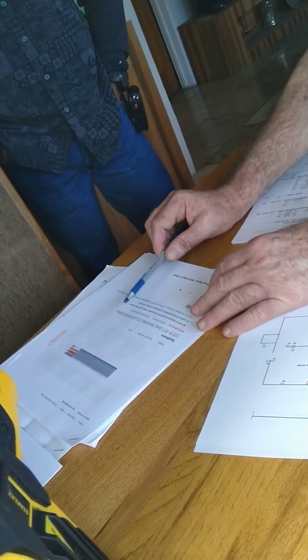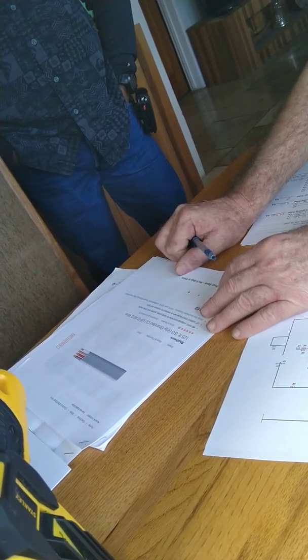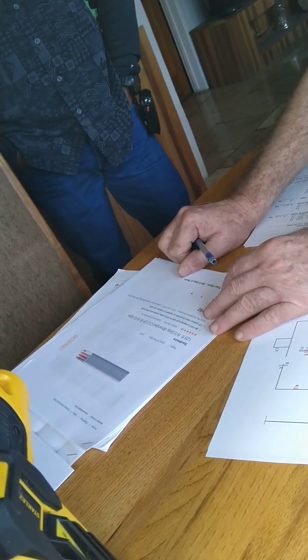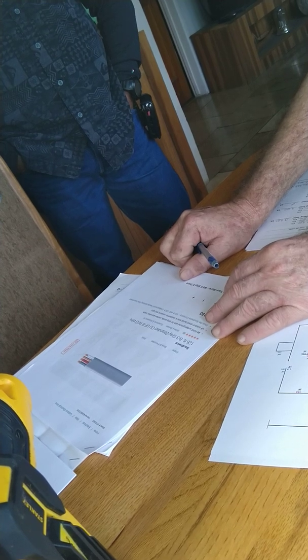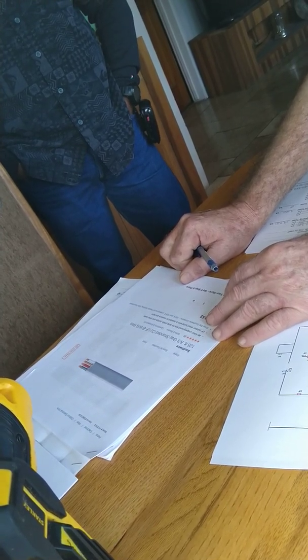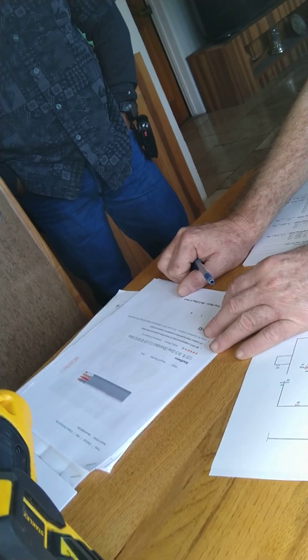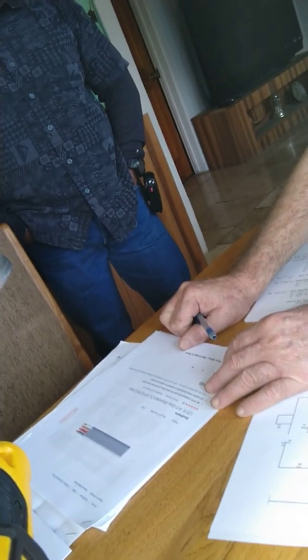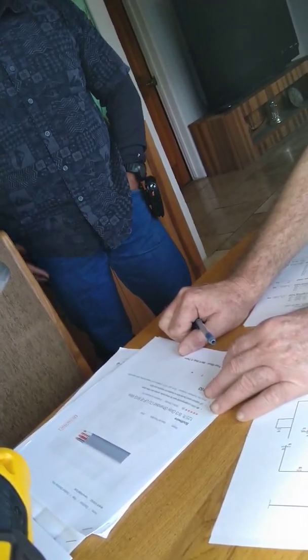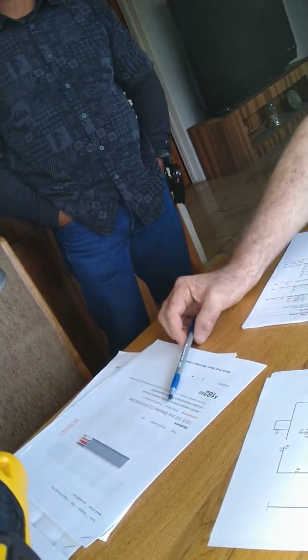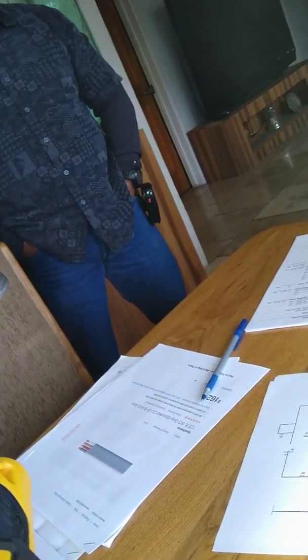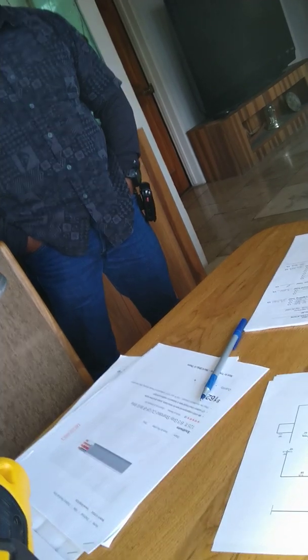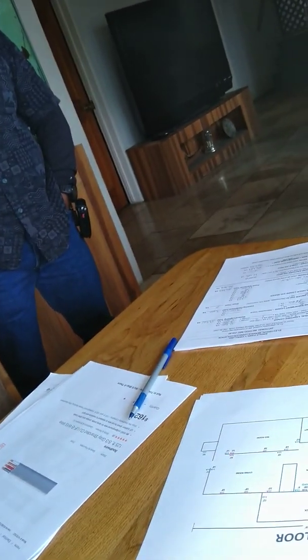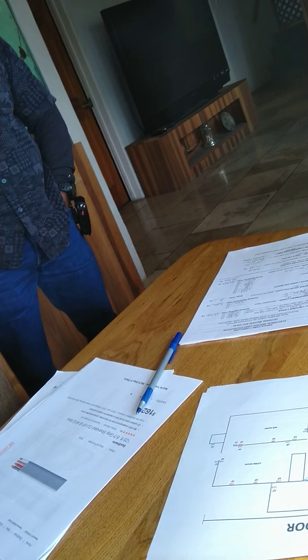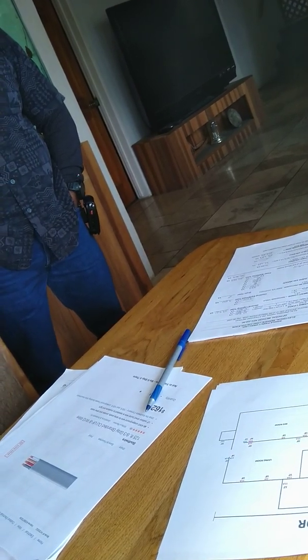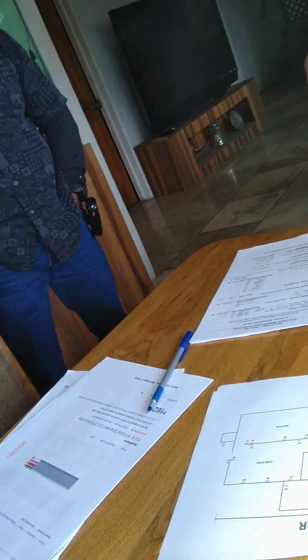Okay, but it also said that it could be exposed to sunshine. Yeah, but you don't want it to be in an area that could be damaged. All right, so something like that is like if you had it underneath a patio cover, it's up high, you're not going to be able to step on it or pull on it or hang something from it. Okay. But if it's low, then it can't be that way. It's got to be protected. Okay. Right now it's just run on the fence, but we can simply dig a trench and put it 2 feet down on basically the same route.